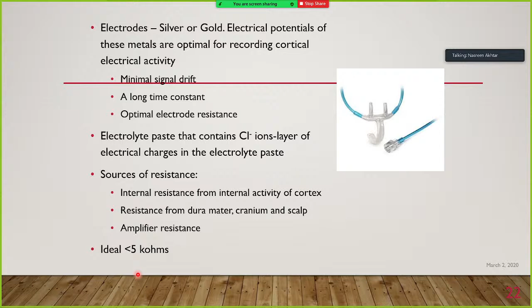So for that we use the electrolyte paste to increase the conductance, and also we prepare the skin: we clean it, we abrade it a bit, all to reduce the resistance so that we can get good signals. Ideally the resistance should be less than 5 kilo ohms. This is the golden number that we look for in polysomnography. Our software will provide the resistance of the electrodes the moment we start the recording.